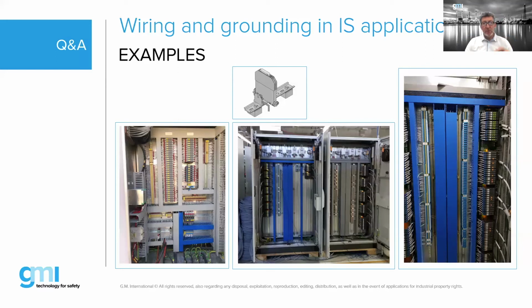There was a live question, Bob, which you can use this picture to answer. They were asking if we can install the barrier on the same DIN rail as other devices. Yes, you can. Again, if you want to mount other devices next to barriers, there is a segregation requirement of 50 mm between IS and non-IS circuits. So if you had a DIN rail with some IS barriers and you wanted to mount some power terminal blocks next to it, you'd have to maintain a separation between them of at least 2 inches. There are some exceptions and things you can use, such as partitions, but generally speaking, yes, you can mount different devices next to IS barriers. Just keep in mind the separation between IS and non-IS.